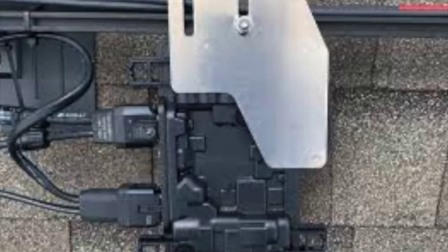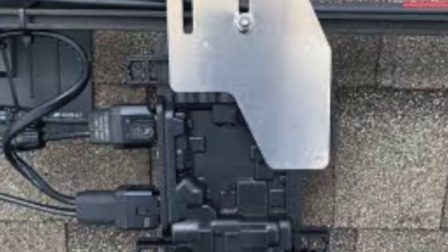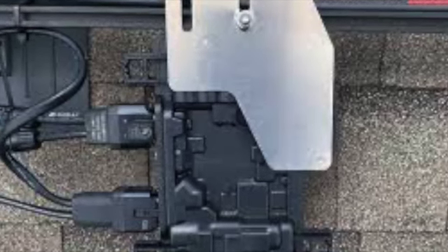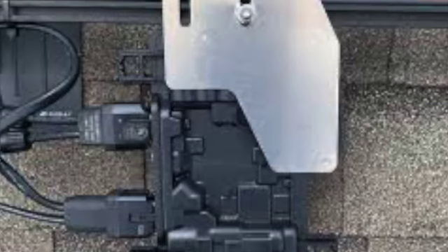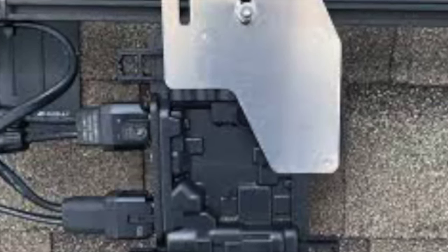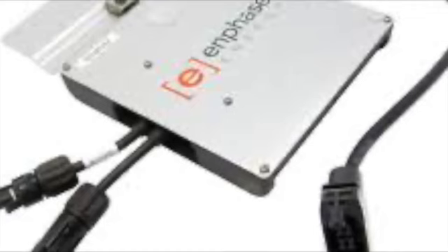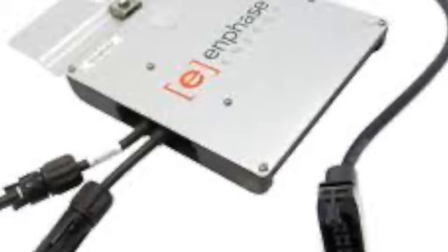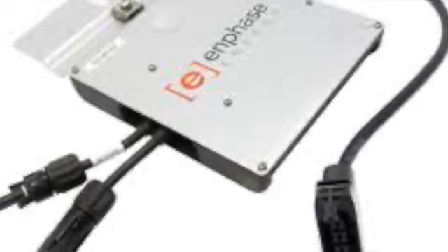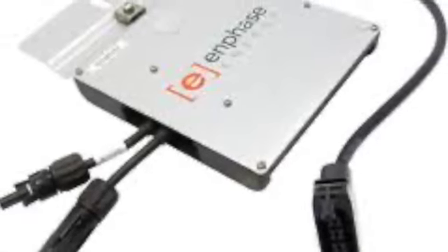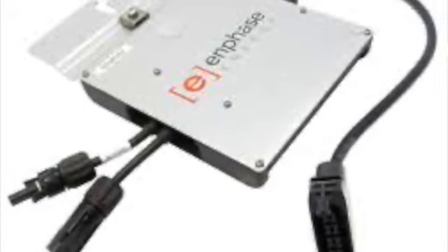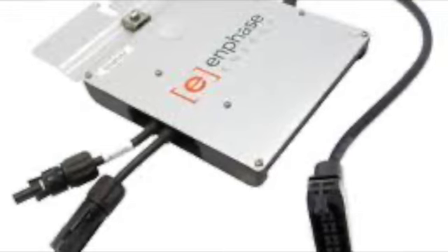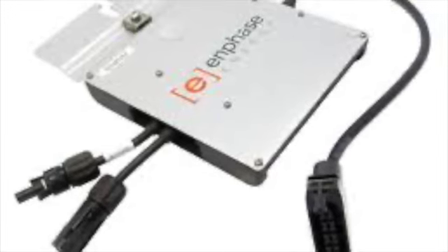Well, with a central inverter, it's more like a team where everyone's tied together with the same rope. If one team member slows down, one panel gets shaded or dirty, the whole team, the whole string slows down too. Wow. Yeah, a single underperforming panel can literally pull down the output of all the other panels connected to that same string inverter. They work best, really shine, when conditions are uniform, lots of sun, no shade. So that independence or lack thereof really highlights the performance difference.